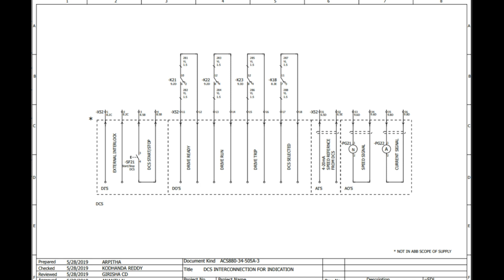Next, DCS selected, what we have seen earlier. Again K18 gets selected, so the PLC will get an indication that yes, DCS has been selected. You can give the start command. X52 again, 31 and 32 are for the 4 to 20 milliamps speed reference. After that, 33 and 34 are for the feedback signal from the panel for speed, for how much speed the drive is running. And the last one, 35 and 36, is for the current signal, how much current the drive is drawing. Okay, so this is how it is completed.